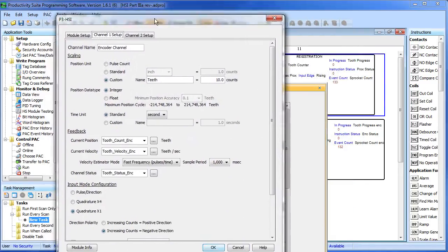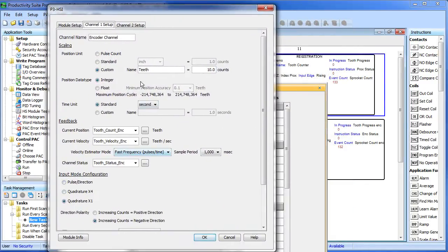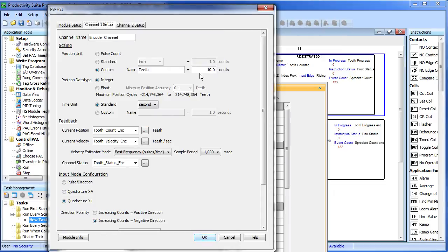Since we're using a 360 count per revolution encoder and we have a 36 tooth sprocket, well that's 10 encoder pulses per tooth so we just put a 10 right here. We need to make sure we specify a quadrature encoder here. If we choose the quadrature times 4 option, then we would simply change this to 40 counts per tooth. Now I know that the way I have this wired, the encoder will give me a backwards count relative to the PROX sensors, so I'm going to invert the polarity here.